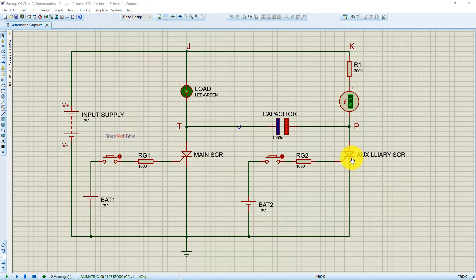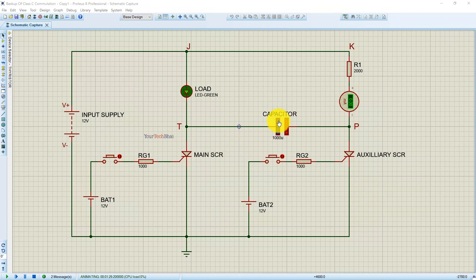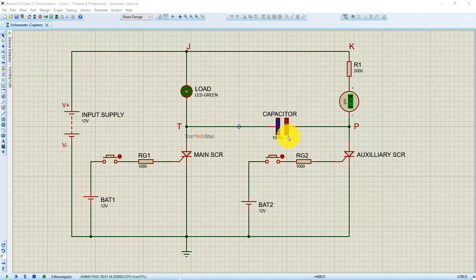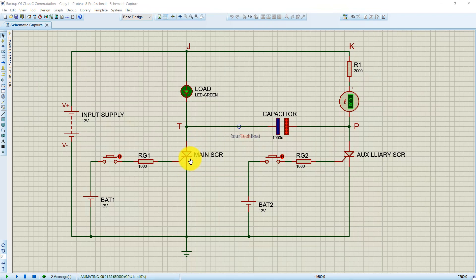To turn off the main SCR, we need to trigger the auxiliary SCR. When the auxiliary SCR is triggered, the capacitor is directly connected to the main SCR. The left plate of the capacitor, which is negatively charged, is connected to the anode of the main SCR, and the right plate, which is positively charged, is connected to the cathode of the main SCR. Thus a reverse voltage is applied to the main SCR, causing it to switch off.